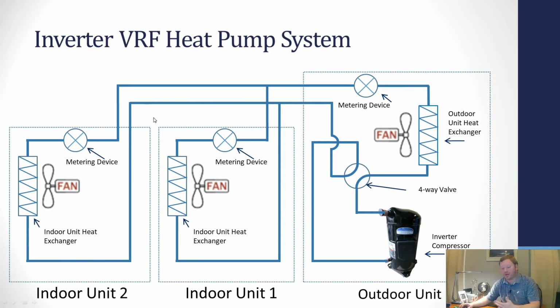But when you go to that VRF, and we discussed this last time, some of the biggest advantages are your controls. And we're just scratching the surface. When we get into the heat recovery section, there's a bunch more stuff we can do that's really cool. But from a residential perspective, one of the biggest things we struggle with every single day is comfort. And when we're seeing mini splits time and time again be oversized or undersized and just really lacking the understanding of how does it work, why is it doing what it's doing, 9 times out of 10 the answer is, well, you should have done a VRF.